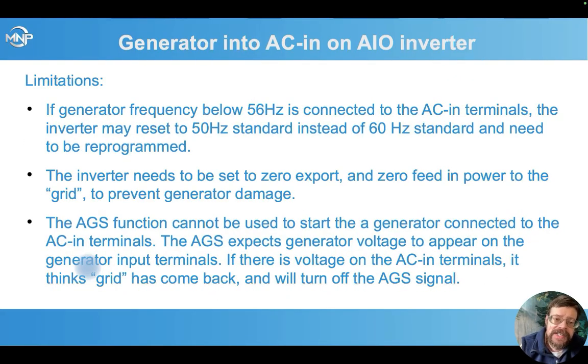One thing to be aware of is if a generator connected to the AC in terminals drops below 56 Hertz, some of these inverters, mostly some of the really early firmware, so if you've got up-to-date firmware, this shouldn't be an issue, but some of the really early firmware, those inverters would reset themselves to 50 Hertz instead of 60 Hertz and have to be reprogrammed by the factory. Can be done remotely, but it's kind of a hassle if your inverter all of a sudden switches to 50 Hertz.